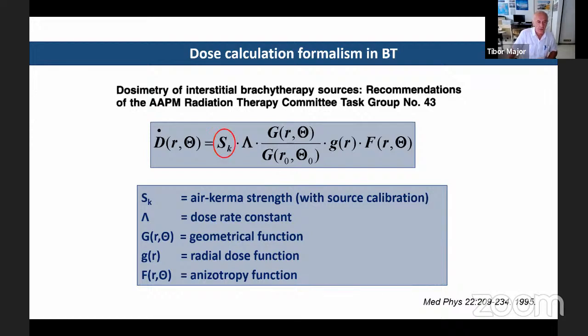So there are a few parameters. The first one is the air-kerma strength. This is what the users have to determine with source calibration. This is the only one parameter which has to be checked by the users after the source replacements. The next parameter is the dose rate constant.